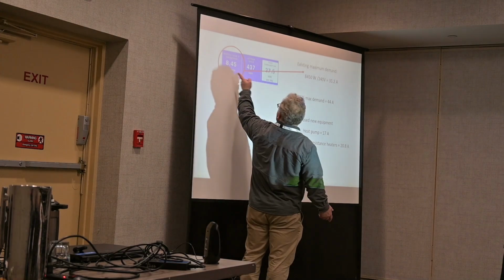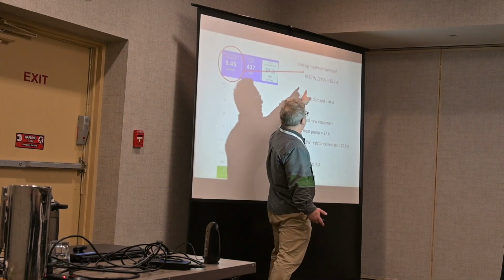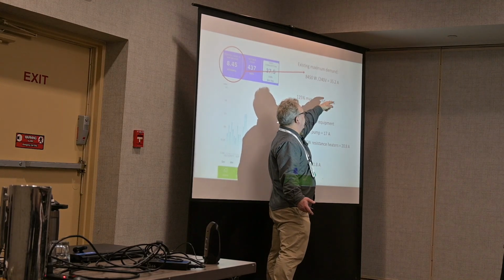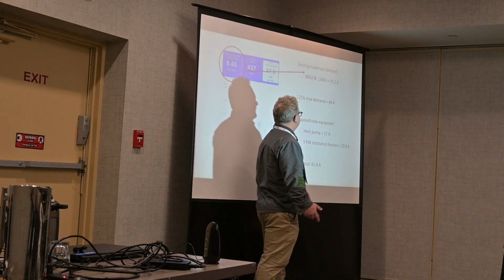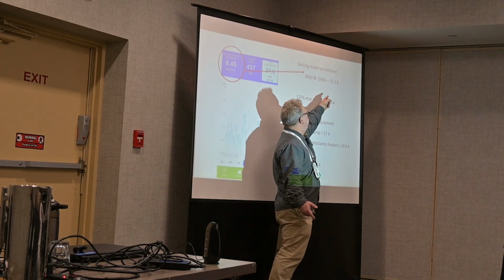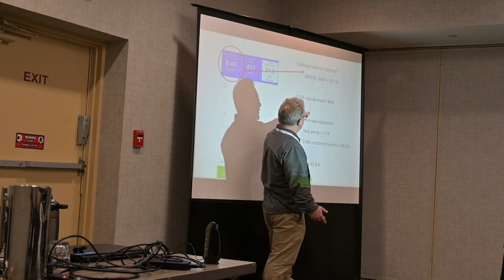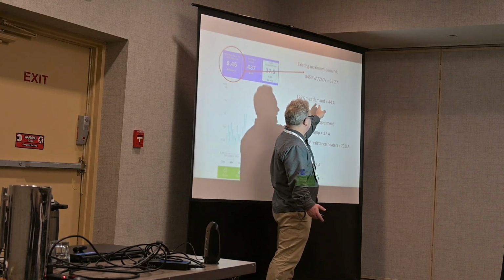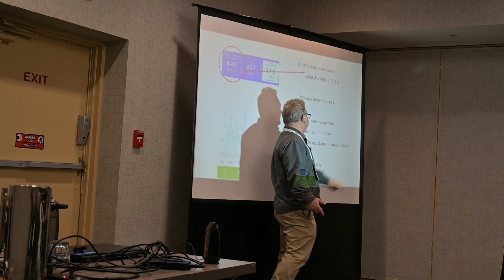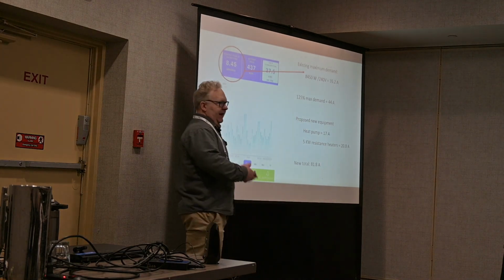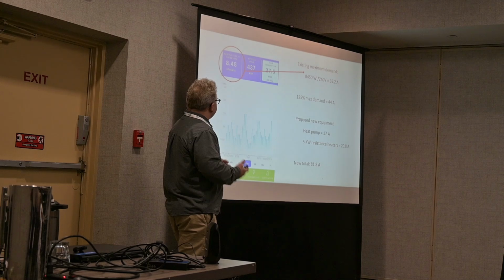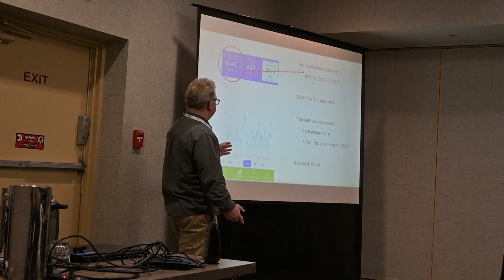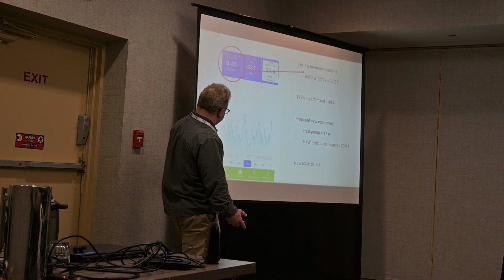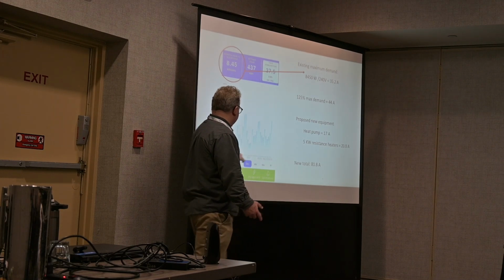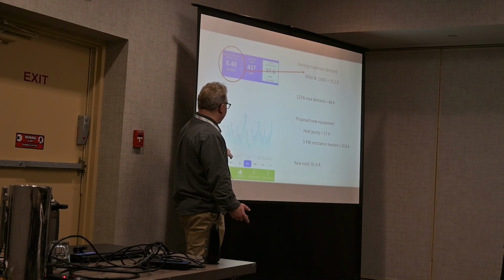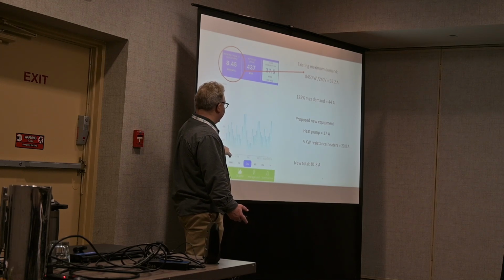So you can take that 8.45 kilowatts, or 8,450 watts, and convert it to amps. In this case, that translates into 35.2 amps. You need to add in the 25% safety factor. That brings you up to 44 amps. So the house, as is, has a peak of 44 amps. This was measured during a season when there was no heating or cooling going on, so it doesn't take that into account.